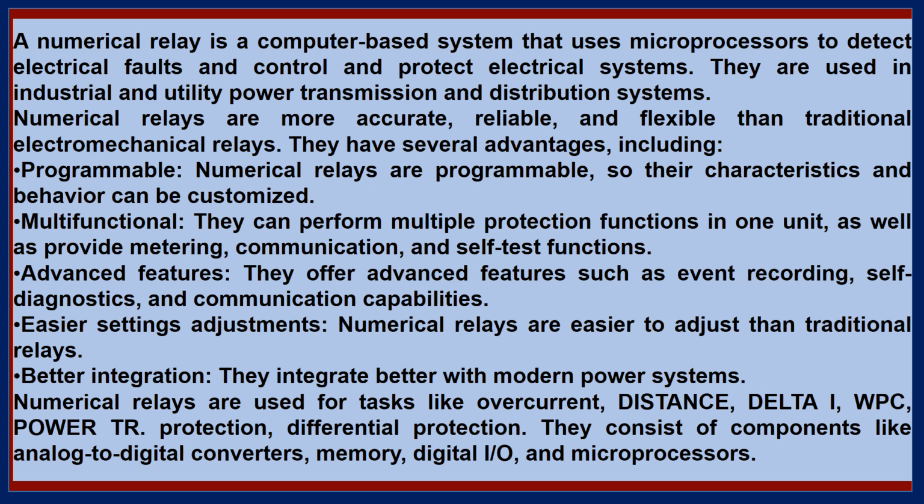giving undervoltage, overcurrent, neutral displacement relay, PT fuse failure relay. So many things can be combined or integrated in a small unit, and as it is microprocessor based, it is programmable and can perform so many functions, so it is multifunctional.